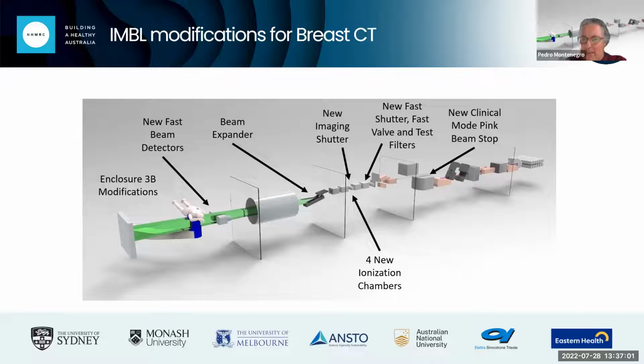It means when we are set up to image a patient, I can activate filters which can increase the beam flux by 10% or decrease it by 10% and verify that the IPAS picks up that change and closes all the shutters immediately. So this is a component which is used to modify the X-ray flux and check that the safety system is working.